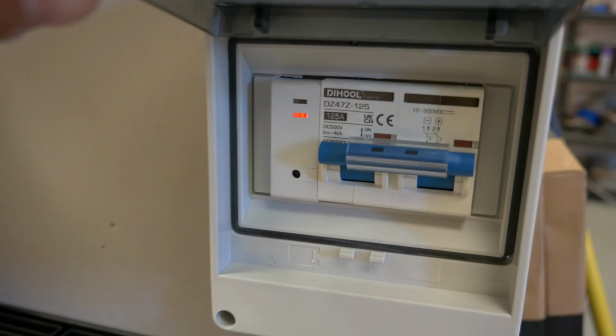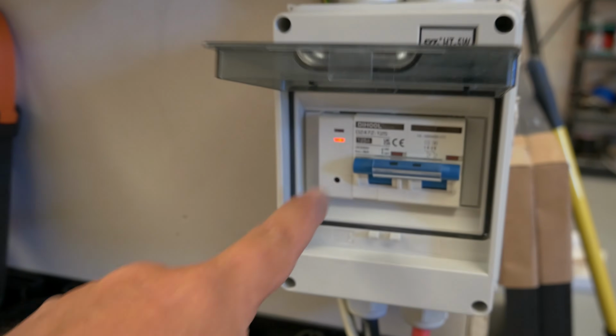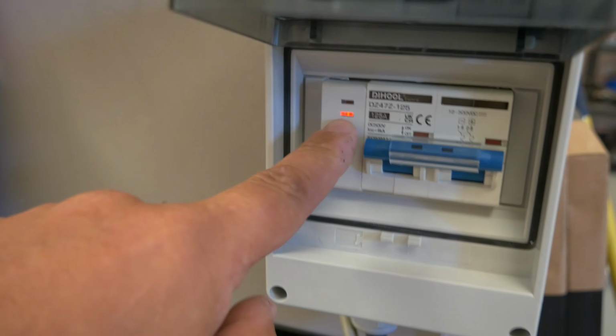We've then got the DC isolator here between the battery and inverter. I actually asked for that in the instruction manual, so we've popped that into position. This is a 125 amp variety, rated at 125 amp, and it served a dual purpose because we can put the gateway in here. This is the device that connects to the internet to make all of this smart, and that runs through a lead up into the comms port on the bottom of the inverter. It was just somewhere to house that. Made sense, there's an extra space in there, and we've kept the cabling underneath free and easy.